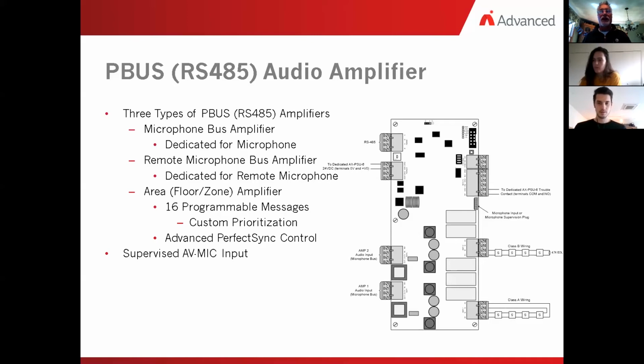Now again, we supervise the mic for the input. If somebody happens to disconnect it or hold the microphone down more than 180 seconds, we'll get a trouble on the panel. All you have to do to reset that is release the microphone and then rekey it, and it starts over again.